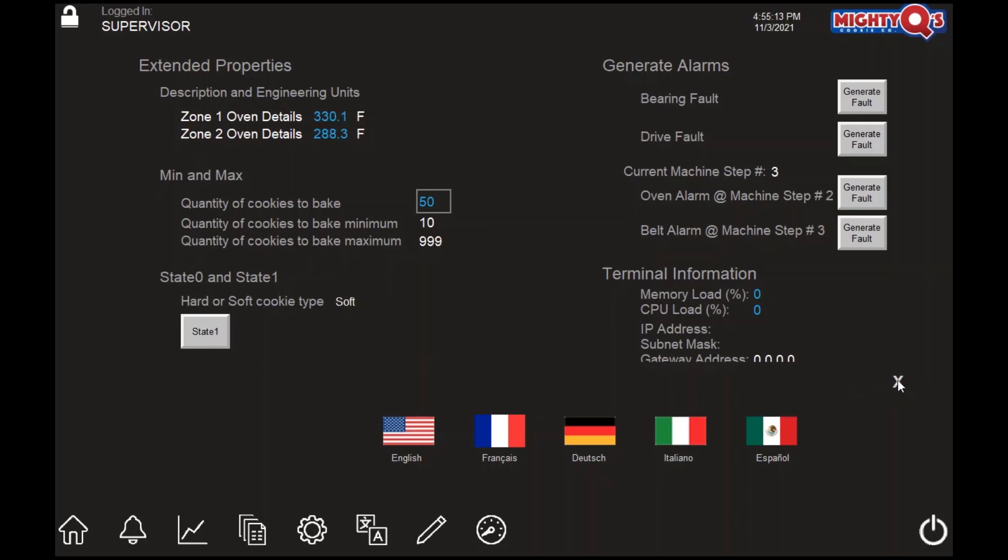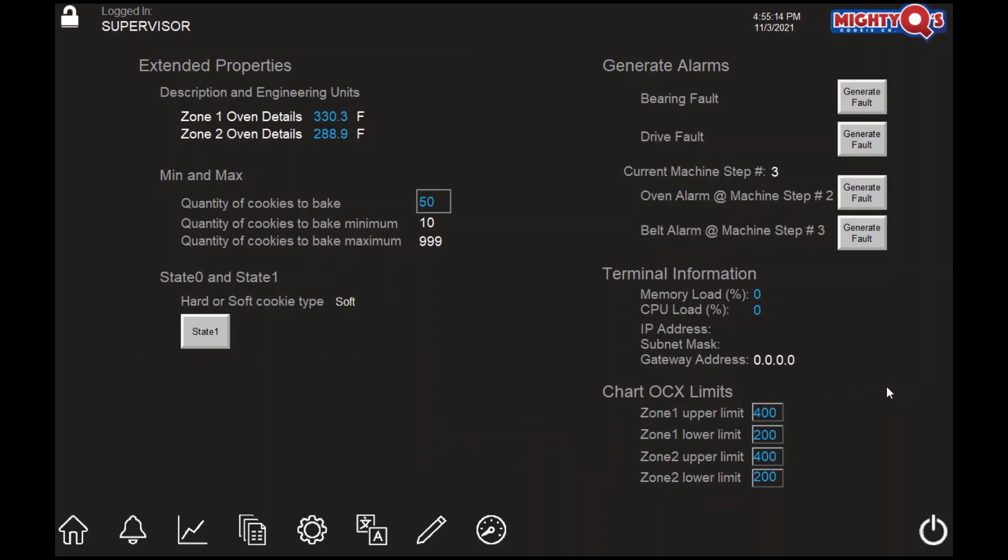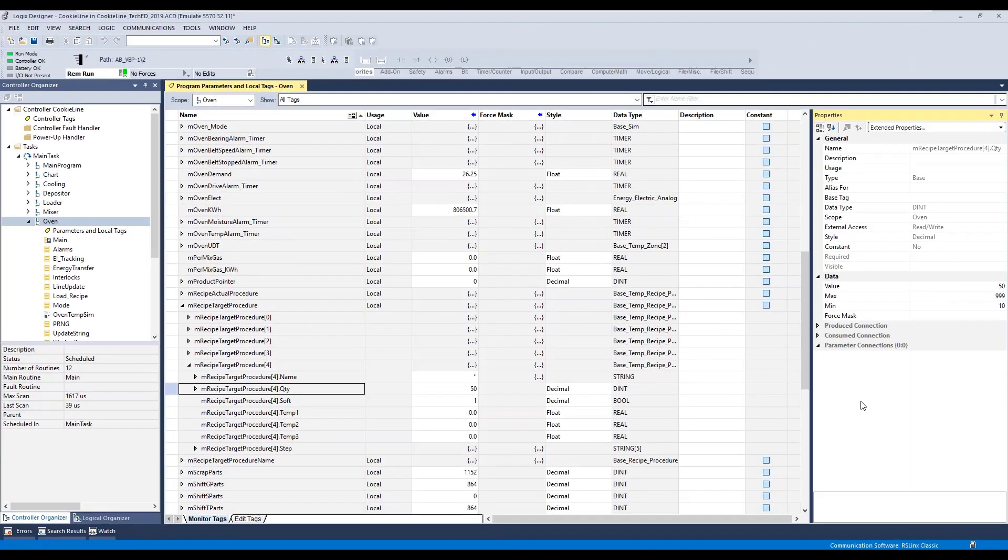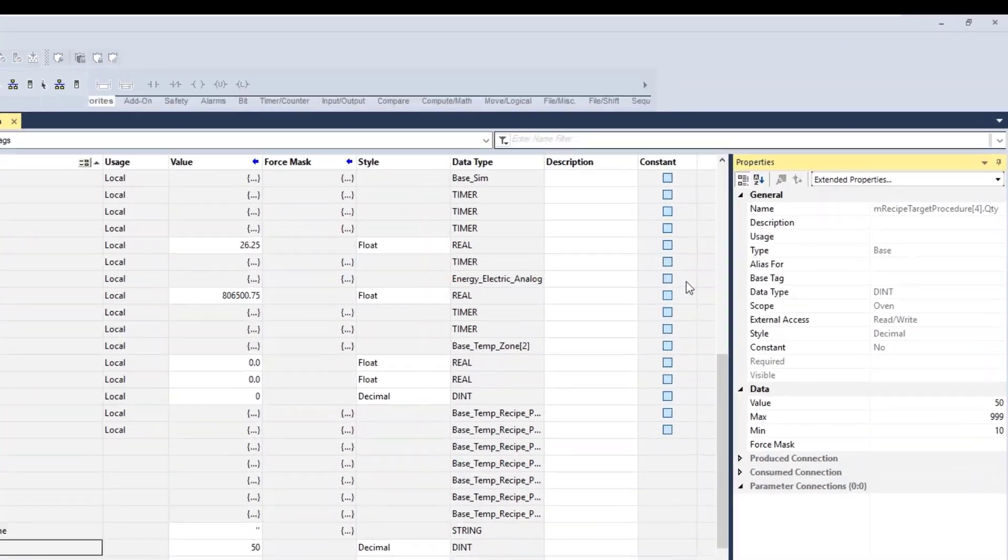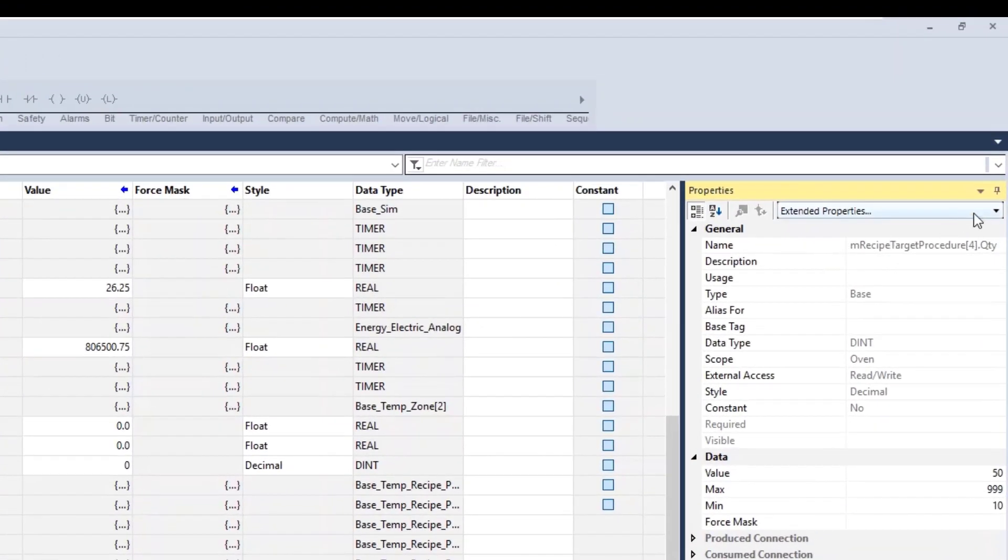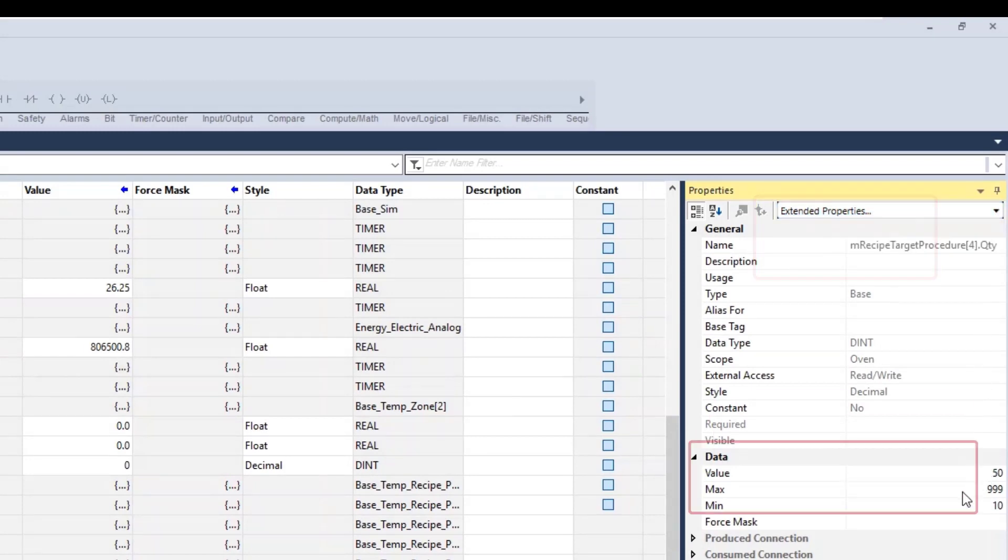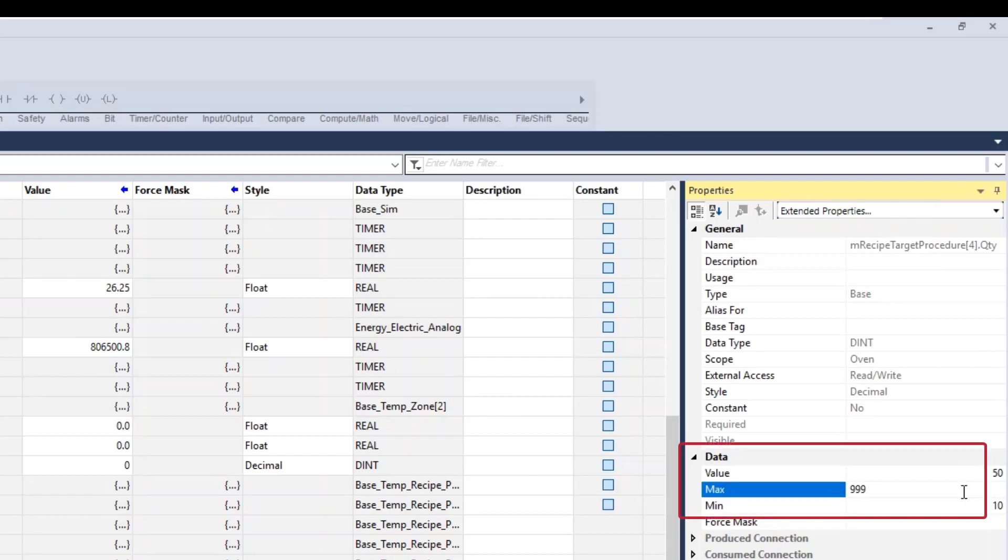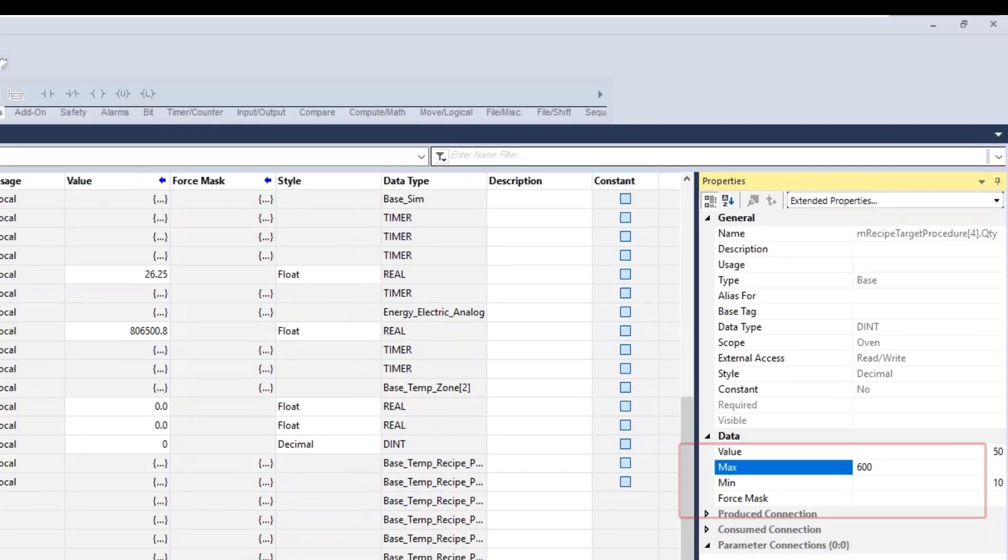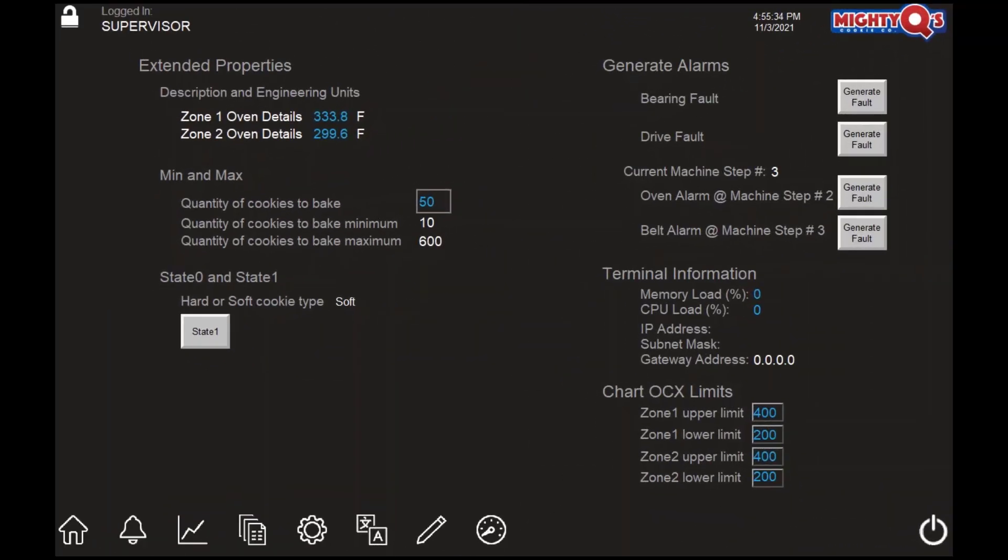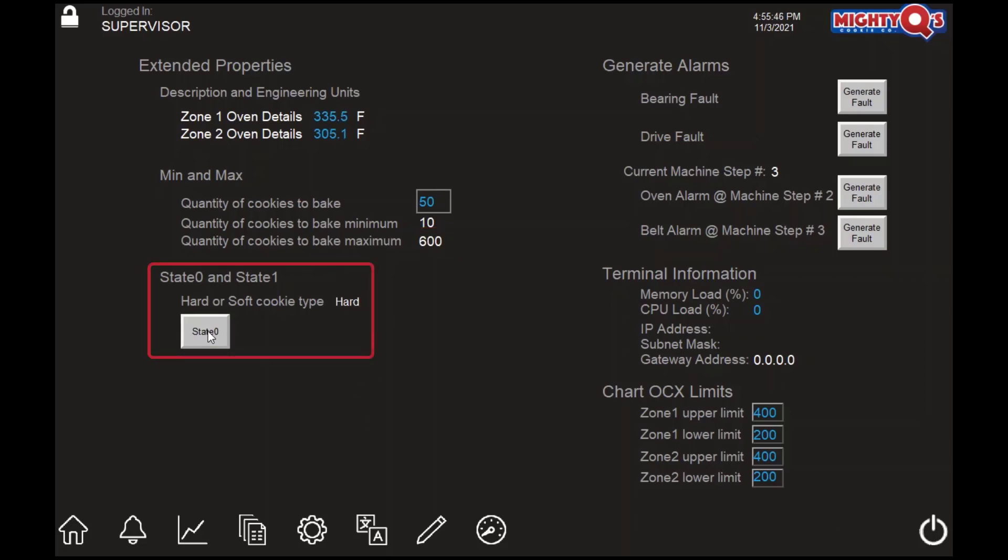Finally, we will return to English and close the pop-up display. With our application still running, let's take a look in Studio 5000 Logix Designer at the cookie quantity tag and examine the extended properties. You can see that the min-max have been configured for this tag. Let's go ahead and change the max value from 999 to 600. Keep in mind that we are not changing the value of the cookie quantity tag, we are changing the value assigned to one of the tag's extended properties. Returning to the FactoryTalk View Machine Edition runtime, we can see that the max value associated with the cookie quantity has been updated to 600.